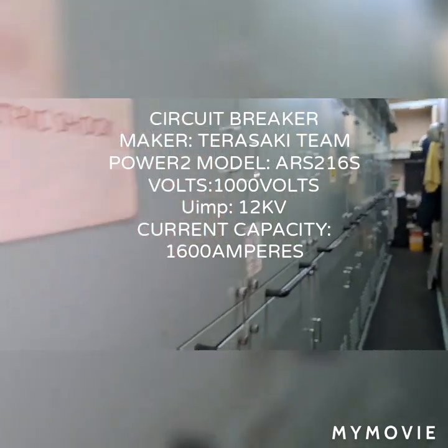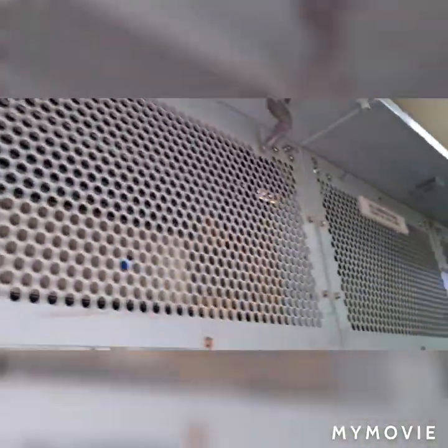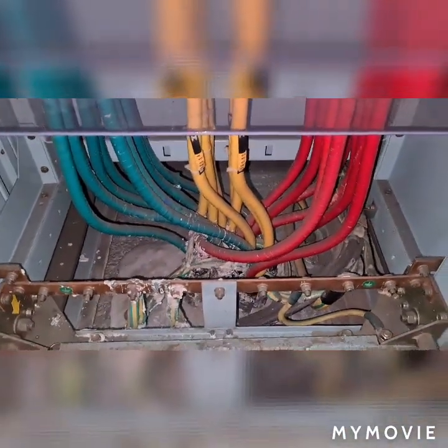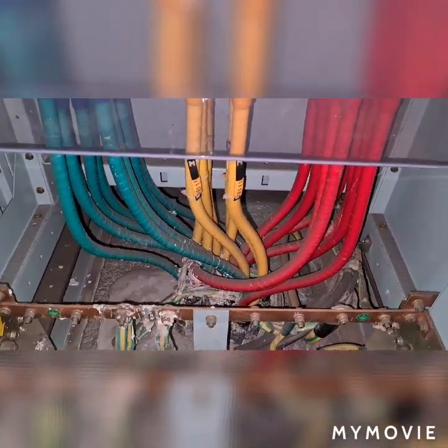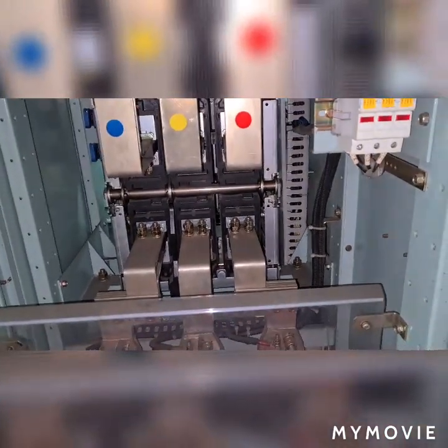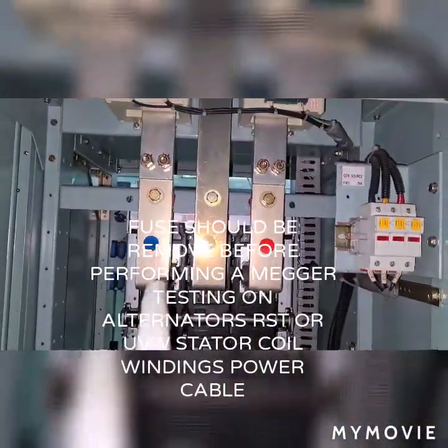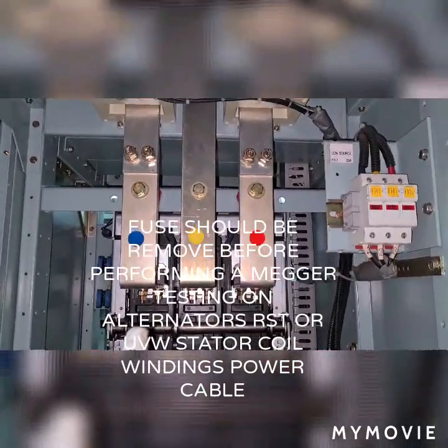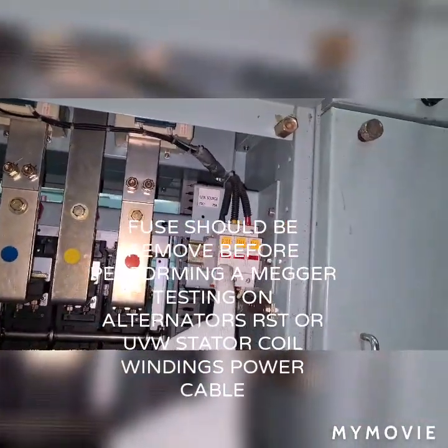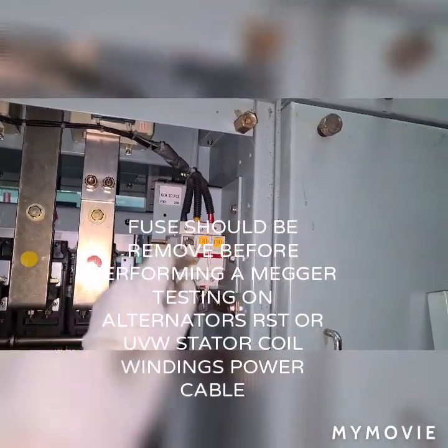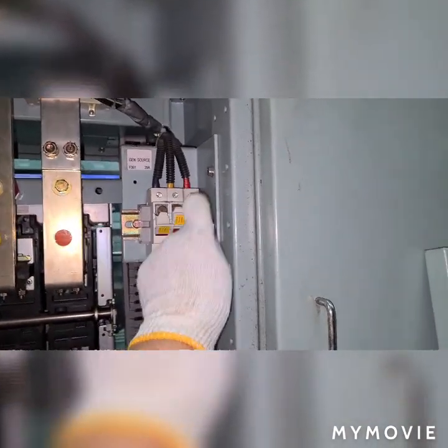Now I am on the back side of my main switchboard inside the control room, and I'm going to isolate the generator voltage fuses. As you will find, there are cables green, yellow, and red, the UVW or also known as RST. This has no voltage because this comes from the generator, and on the upper side there is a bus bar, blue, yellow, red. This is live, with 450 volts connected on the bus bar. These are the fuses which I'm going to isolate before I proceed to the alternator side to isolate the AVR before proceeding to do a Megger test.